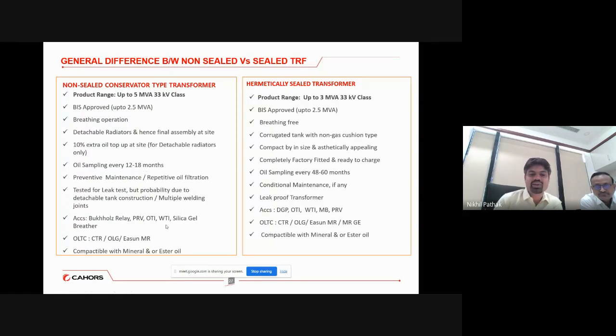Every 12 to 18 months, the sampling of a conventional transformer has to be done, because periodically the healthiness needs to be maintained as per factory license and the regular norms and compliances also. However, for sealed type transformers, we are confirming that oil sampling can be done within every 48 to 60 months. Every 4 to 5 years, the oil sampling is to be done, and then the proportional corrective action can be taken accordingly. So the non-sealed design transformer requires preventive maintenance and repetitive oil filtration, which is a cost for any customer.